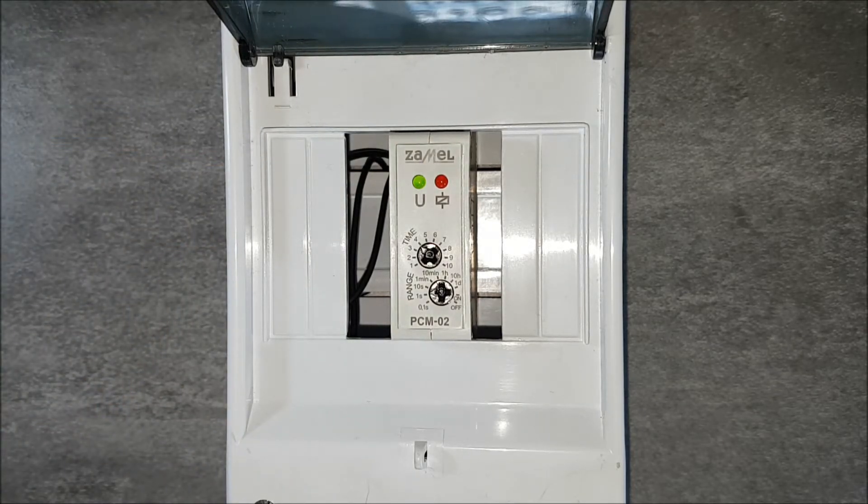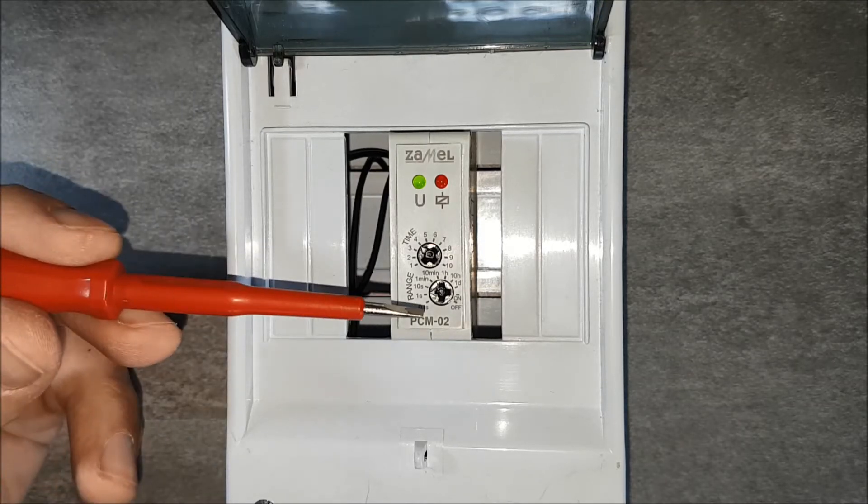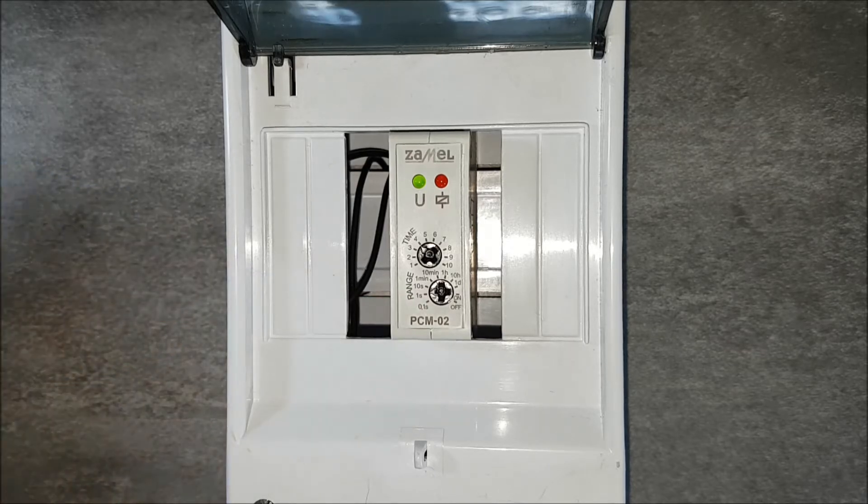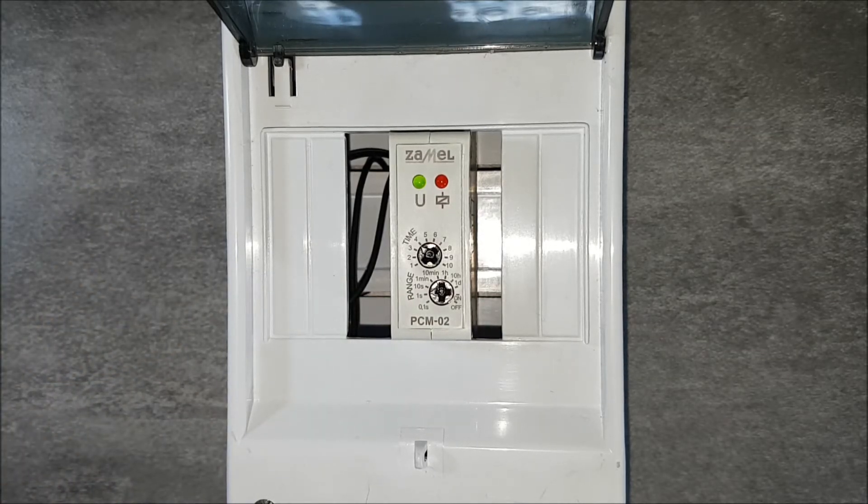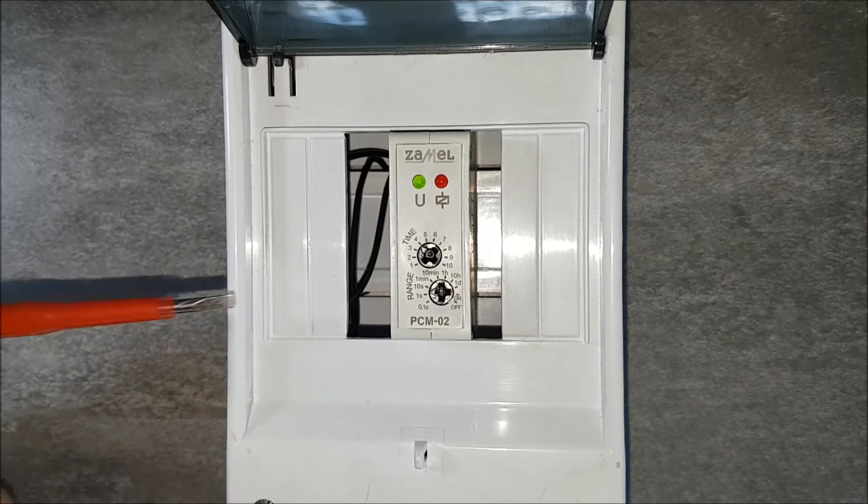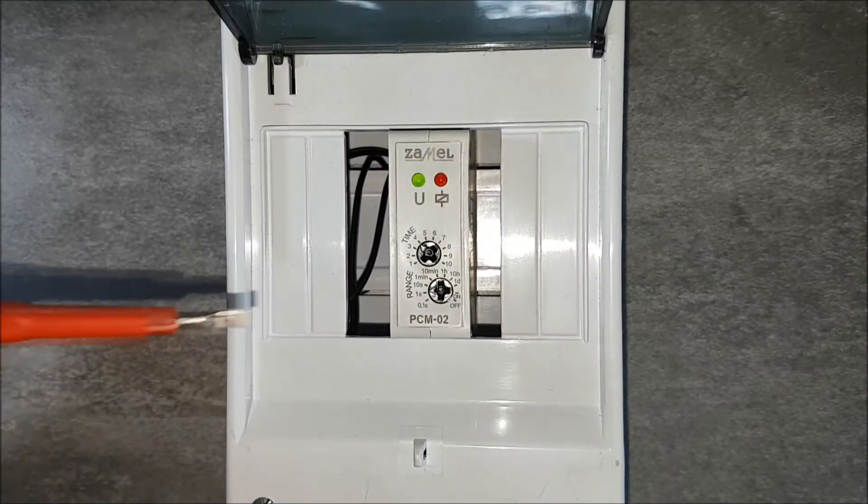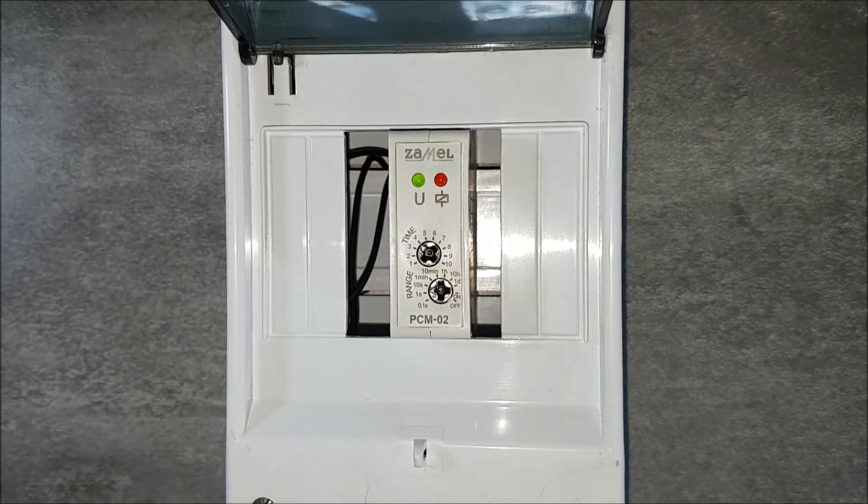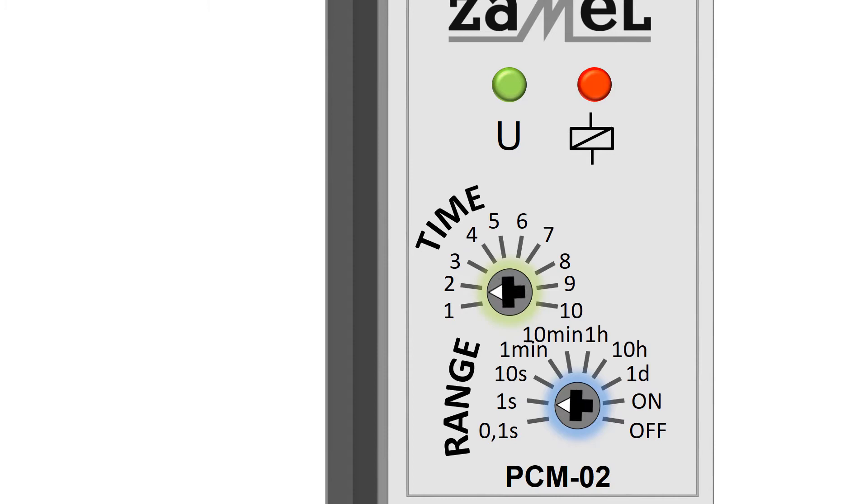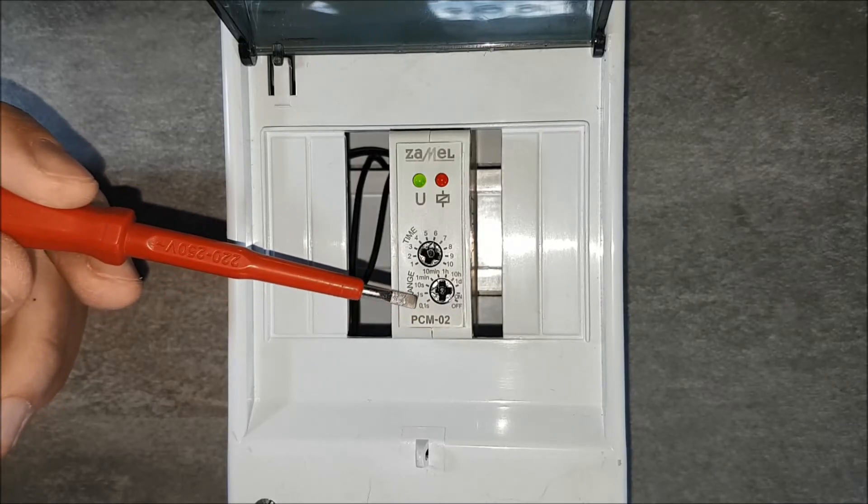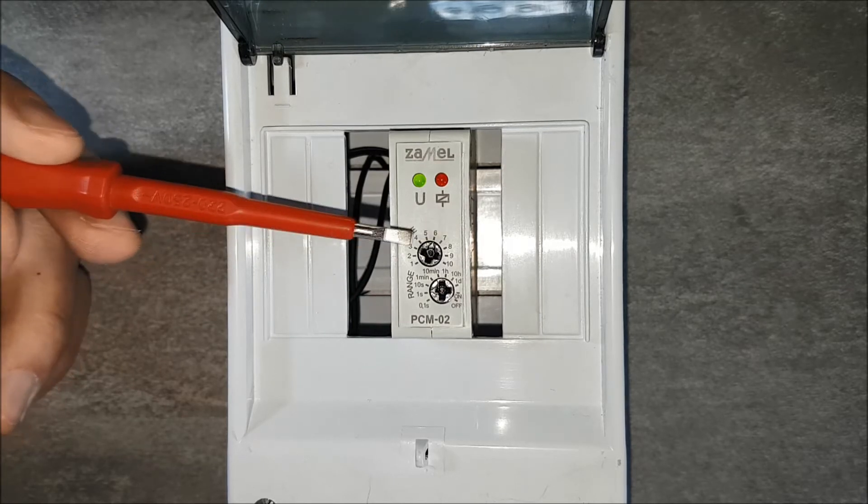Set the selected time. First set the time base. For example, set the time of 6 seconds as the basis of time, so choose 1 second first. Then choose the time multiplier, in this case number 6. As a result, get the set time: 1 second multiplied by 6 equals to 6 seconds.